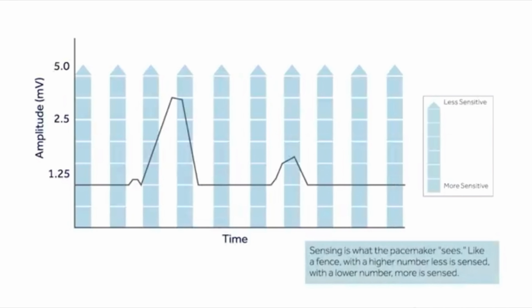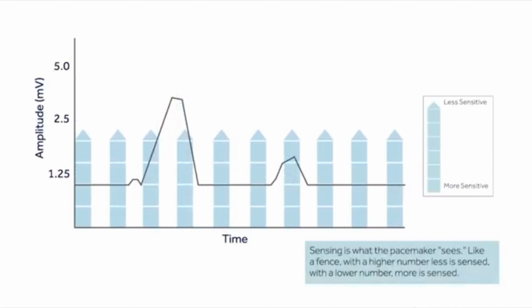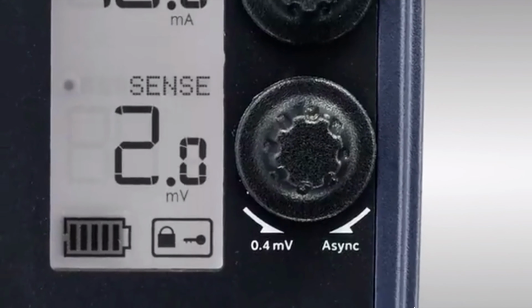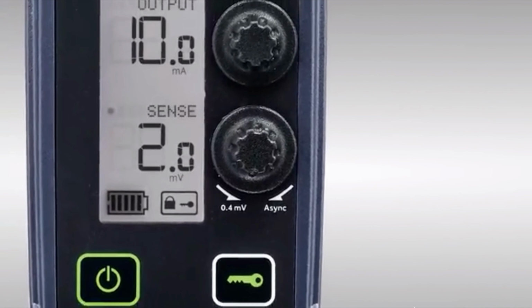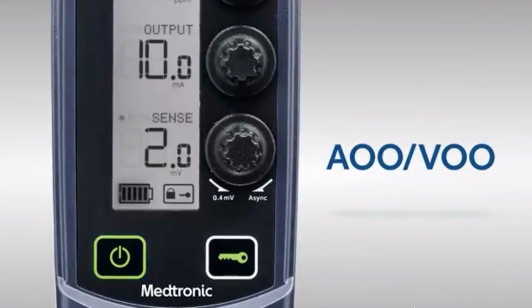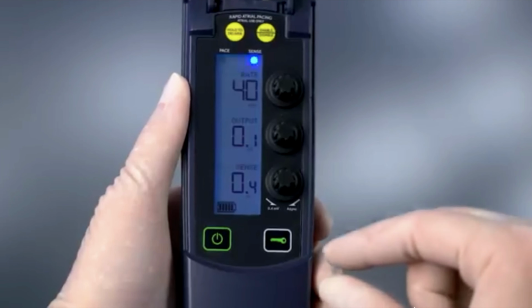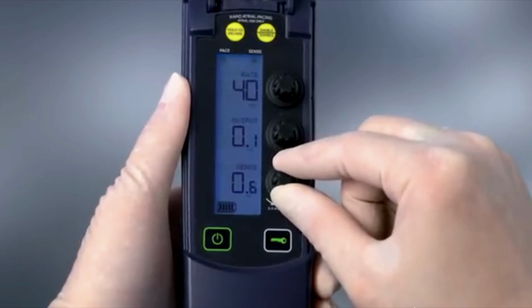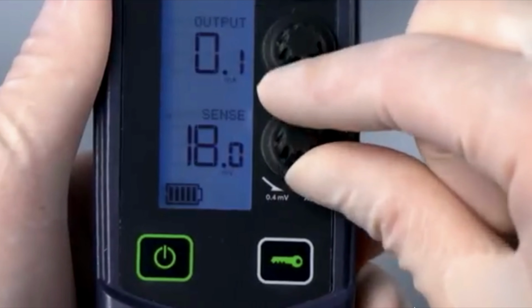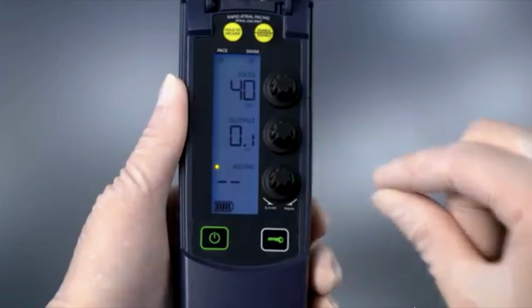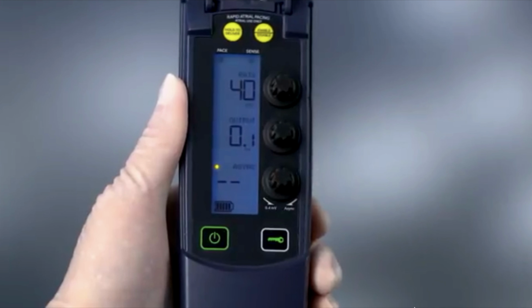Recall the definition of the sensing threshold is the least sensitive setting at which the pacemaker can detect a heartbeat. The sensitivity setting allows you to control the pacing mode between synchronous or demand pacing and asynchronous pacing, also referred to as AOO, VOO. Notice the range on the sensitivity dial goes from the most sensitive setting of 0.4 millivolts to a setting labeled async. When set to async, the sensitivity is set to a value so high that no underlying intrinsic signal can be detected. Therefore, to pace asynchronously, set the sensitivity dial to async.